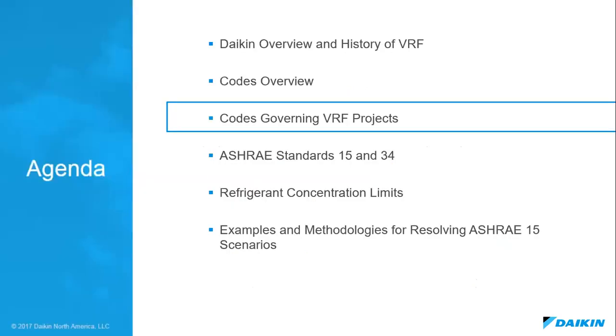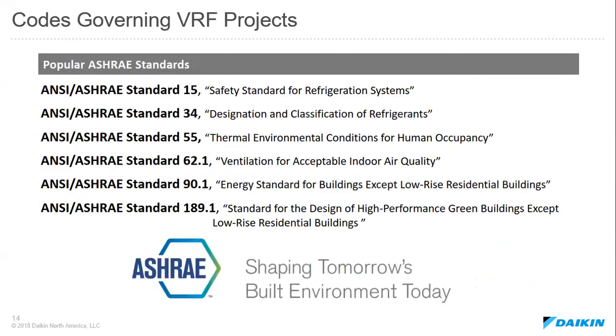Codes governing VRF projects. There are a long list of about 20 different popular codes, and here we've listed several of these codes that get used on a regular basis. Today I'll be talking about ASHRAE Standard 15, which is the safety standard for refrigeration systems. And it's hard to talk about ASHRAE 15 without talking about ASHRAE Standard 34, which is the designation and classification of refrigerants.